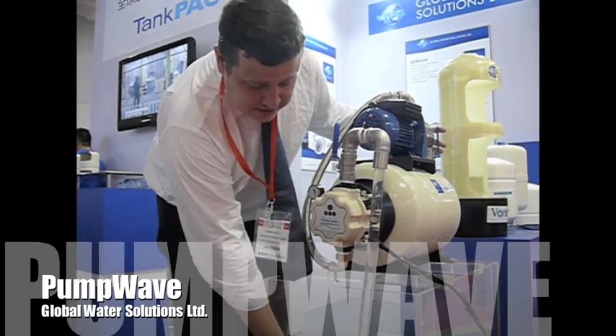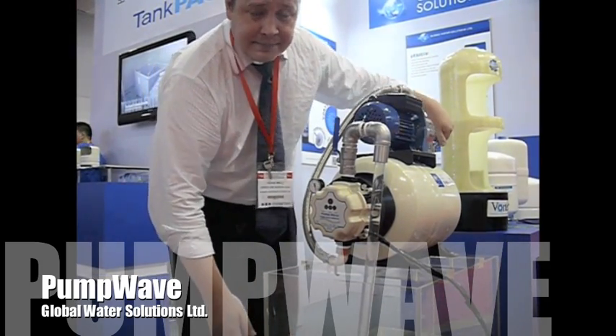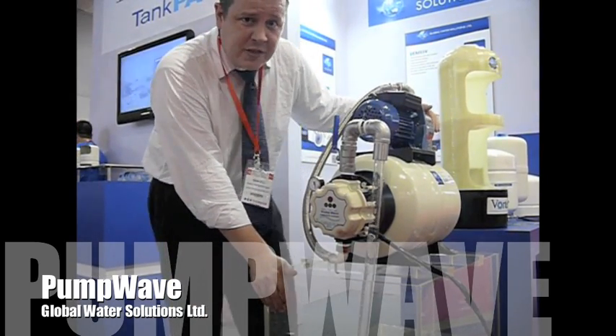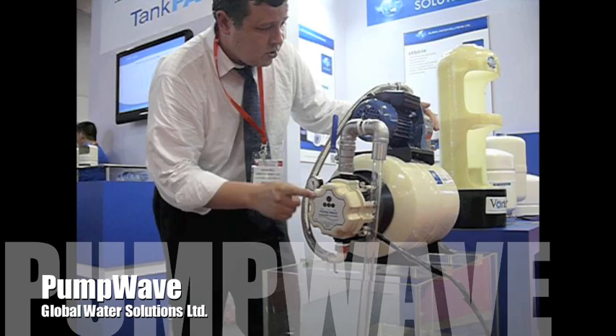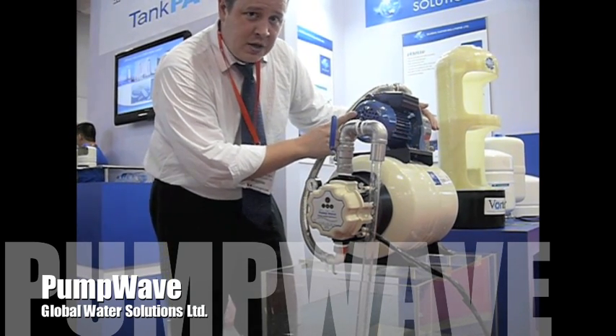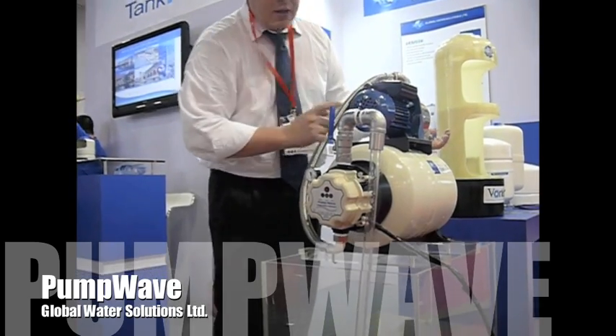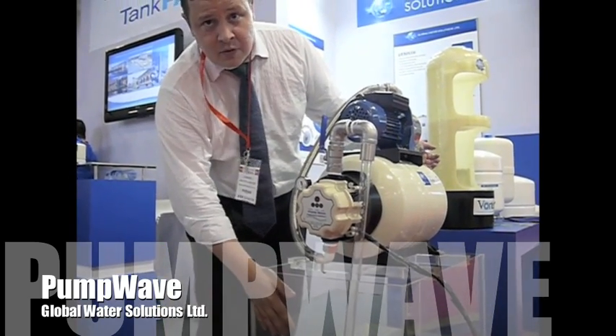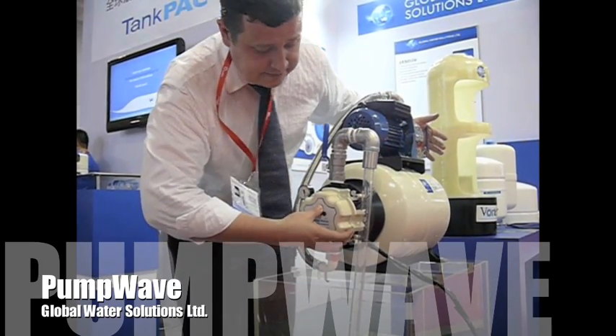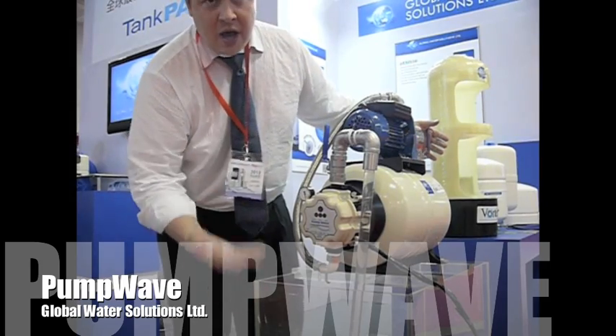Let's say, for example, that this tank goes dry. Once this tank runs dry, no water will be running in the pump. In order to prevent the pump from dry running, the PumpWave device will send a signal to the pump and shut it off, just to prevent it from dry running and burning up the pump. Once we've refilled the system and resupplied the pump with water, you can come back and press the reset button again. This will allow the pump to restart and operate accordingly.